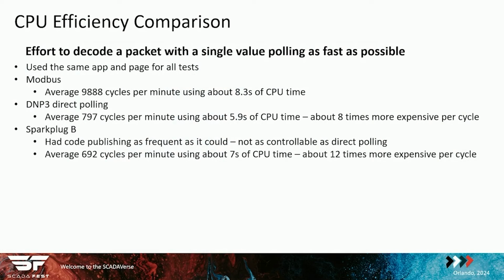The other thing I want to talk about was the effort to decode a packet with a single value polling as fast as possible. So I hooked up some devices we have in our lab and talked to them, just seeing how much data I can bring in, and how much effort that takes on the CPU within VTScada. This can actually be done within VTScada using the profiler tool. So that's where all the test data comes from.